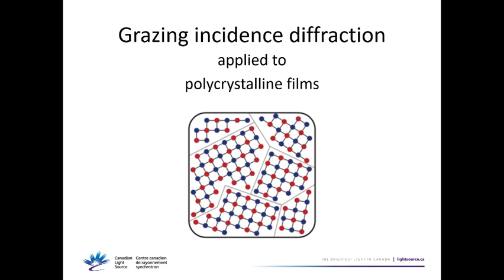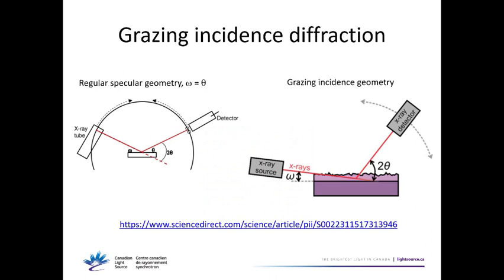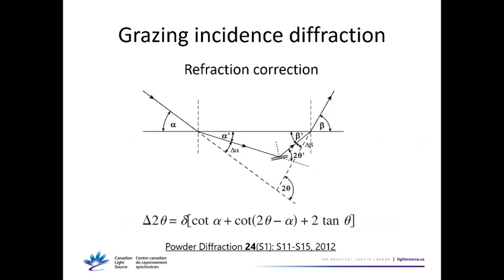If your sample is polycrystalline, you can do grazing incidence powder diffraction — the same powder diffraction normally done in θ-to-θ scans, except you keep the incidence angle fixed at a very grazing angle to be more sensitive to the thin film, and sweep the detector in 2θ. In this geometry there are several corrections including absorption, Lorentz-polarization, atomic scattering factor, and importantly refraction — the beam refracts at the surface causing a shift in diffraction peak positions that is more significant at more grazing angles.